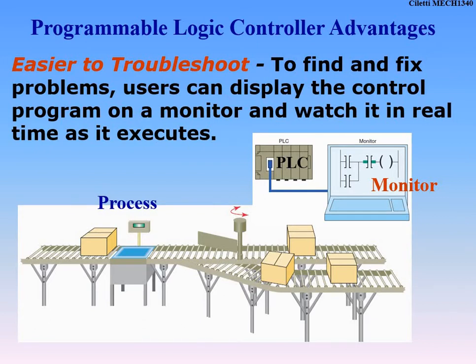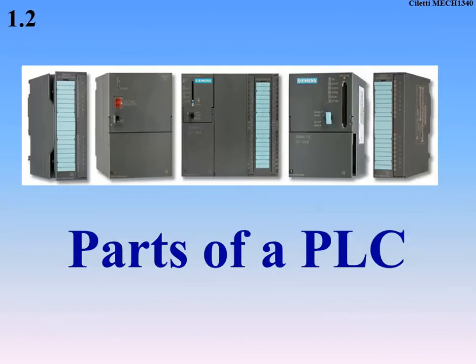We can see what's going on when we monitor the program live as it's working. You guys are going to see that when you start programming the PLCs — you get to program station one as your final. You can see where it's stopping and what's making it stop. It's very nice that you can tap into the PLC and see where the program's having issues. The PLC won't say 'this sensor's out,' but it tells you that something's happening — that sensor's either not getting or not producing the signal — which helps you fixate on that specific sensor.